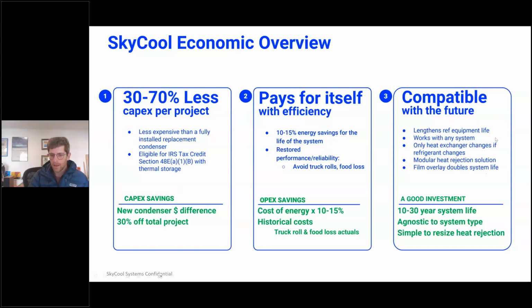And then the third way to think about it is it's compatible with whatever cooling system comes in the future. So right now there's a lot of flux happening with cooling systems. If you think about the transition from high GWP refrigerants like 404A and 410A to lower GWP or ultra low GWP refrigerants, there are a lot of changes that need to happen to this cooling equipment. And so because we only interface with cooling systems using a heat exchanger, it's easy to swap out that heat exchanger in the future if that's a change that is going to happen out of site. And so you don't have a stranded asset issue like you would have today with, for example, HFC cooling systems.